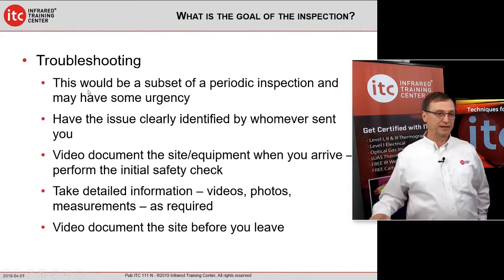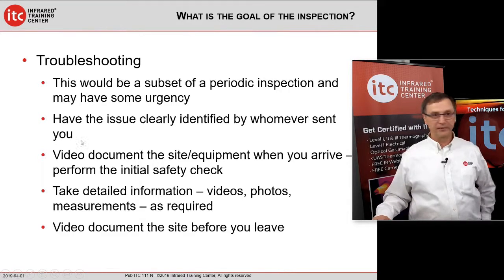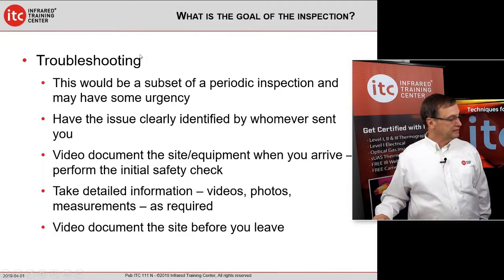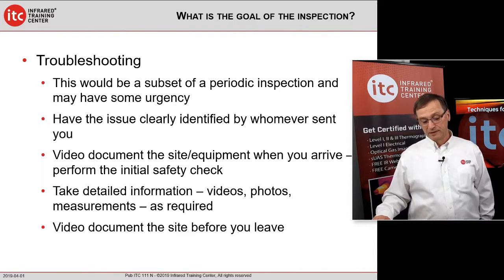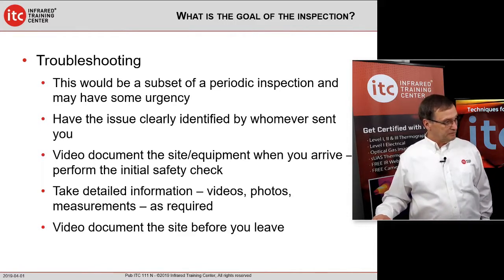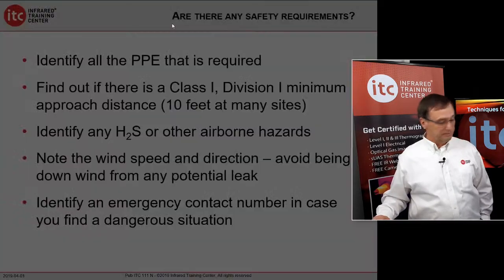For troubleshooting, sometimes you're just required to go out there and there's been an alarm for a leak. Clearly have the issue identified before you get up there to make sure that you can document the site and document the leak. And again, if you're out there for troubleshooting, maybe or maybe not, there'll be a large leak to worry about. So video document the site before you leave, and if perhaps you go out there to locate the leak and then repair it, you should video before you leave of what was repaired.